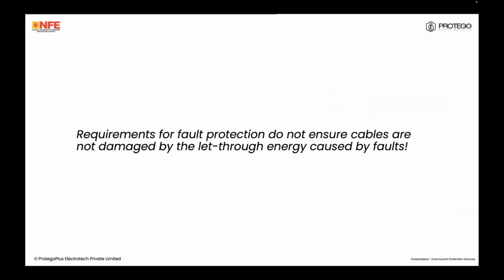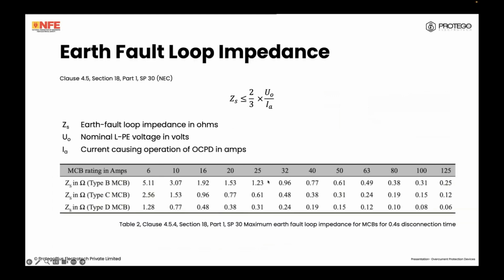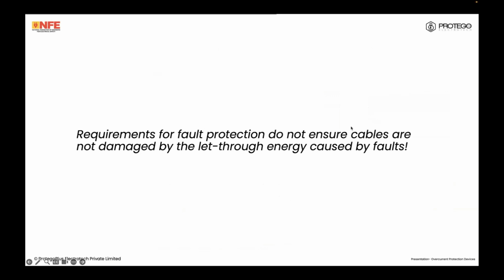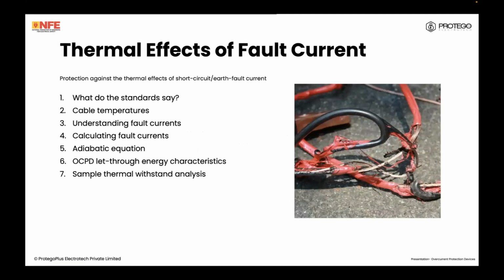Okay, another important thing is requirements of fault protection. Just by achieving these loop impedance values, it does not ensure that the cables are not going to be damaged by the let-through energy caused by the faults. So this is the thermal effects of fault current. Protection against the thermal effects of short circuits or earth faults of negligible impedance basically is what we're going to look at. This is broken into 7 sections.